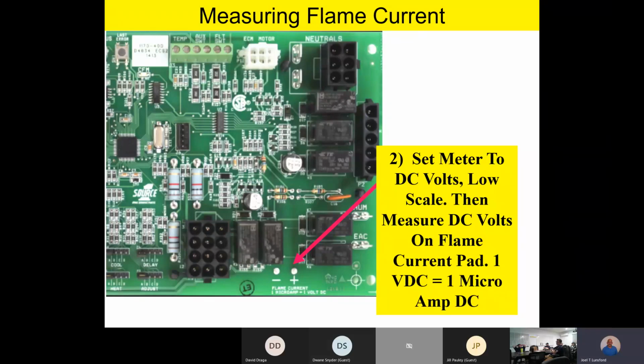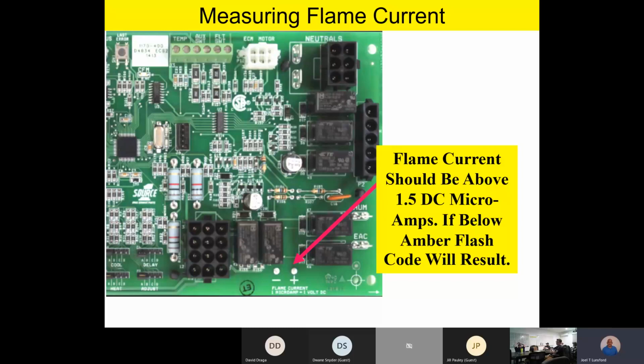Typical flame current on these furnaces runs somewhere between about 2.5 to 4. If you take a look at the service information, I think they'll tell you 3. But it's been my field experience that normal flame current runs about 2.5 to 4. Now it should be noted the flame current has to be above 1.5 microamp. If it's below 1.5 microamp, it's going to generate an amber flash code to tell you that you have low flame current. So 1.5 is the threshold where you get the flash code.